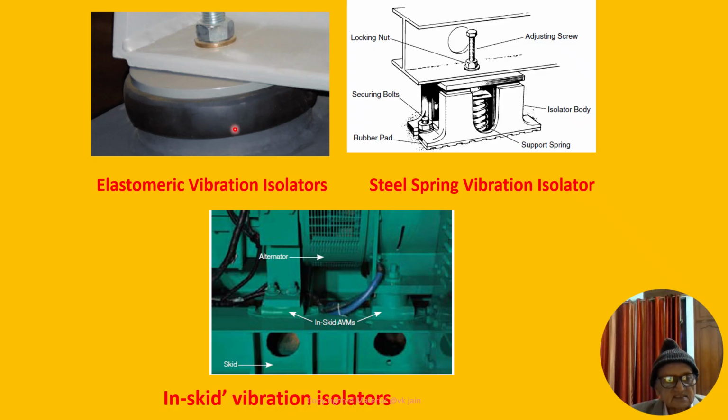In this slide, mounting details of elastomeric vibration isolator or steel spring vibration isolator are shown, and the bottom diagram shows how they are placed in case of the foundation. The skid is provided when the entire diesel generating set is mounted on a skid.